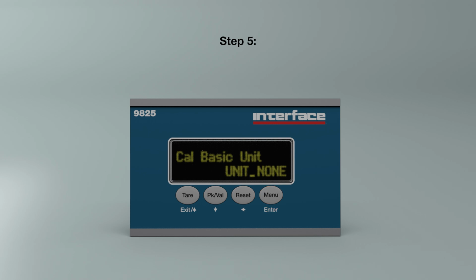Step 5. After confirming the unit selection, the Cal Basic Unit menu item will be displayed again. Press the menu key to scroll right to the next menu item called Nominal Capacity. Press the peak and valley key to edit the nominal capacity value. For this example, we will set a nominal capacity of 40,000. Use the reset key to move left through the digits. Use the tare key and peak and valley key to increase and decrease the value of a selected digit. Once the nominal capacity value is set to 40,000, press the menu key to confirm the setting.